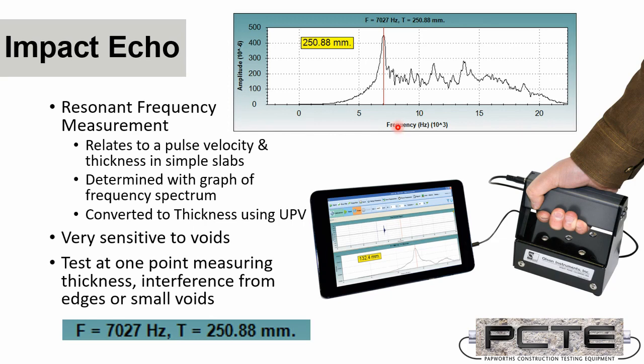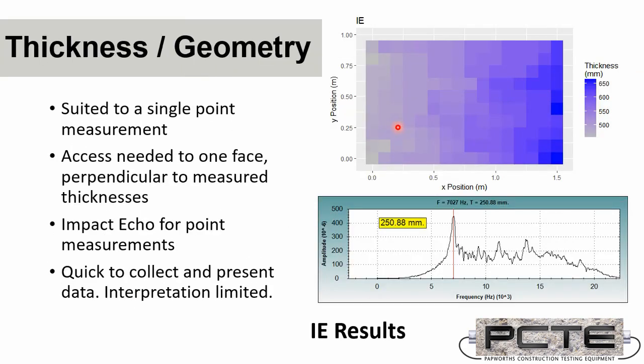Now, one of the big advantages of Impact Echo is it's quick, it's simple, and it's very sensitive to things that change the geometry of that slab. So if you have small amounts of voiding inside a flat plate, it will detect them. And this is what we take advantage of when we use void detection. At its most basic measurement, it's a thickness test. We only need one side to access the slab.